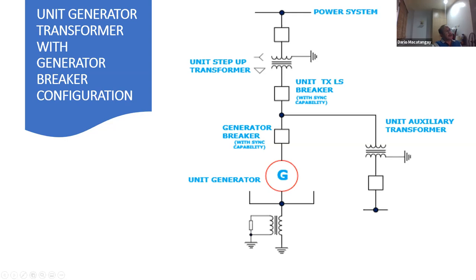Another good thing here is that, let's say you have a fault on the generator, okay? If you have a fault on the generator, what you can do is just trip this breaker here, right? And once this breaker is tripped, the system will just power the unit auxiliary transformer. So you still maintain service, right? Then once you find the fault and correct the issue, all you need to do is synchronize this breaker.